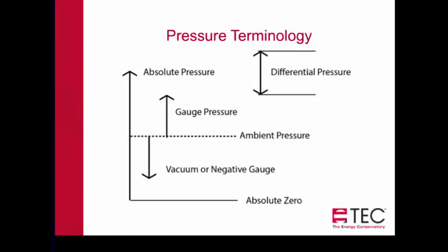Everything measured from absolute zero is an absolute pressure value. Then there's ambient pressure, which is what we mostly deal with — it's around us and affects our everyday life. When we attach a gauge and measure compared to the surroundings, that's considered gauge pressure, or a negative pressure, or vacuum pressure. Differential pressure sits off to the side because it's not really on the scale of absolute or ambient pressure — it's just measuring the difference between two points, such as room to room pressure.